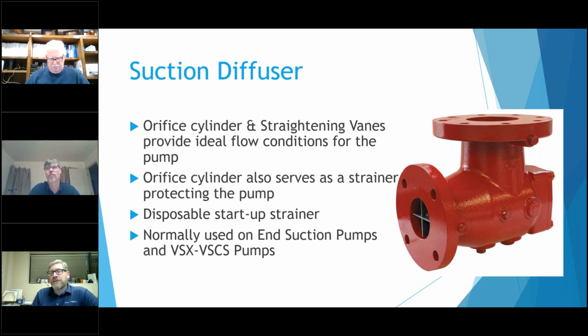Basically this thing's job is just to provide a good flow condition into the end of the pump. If you don't have that good flow condition, you end up stressing out the bearings and the seals, and you end up pushing on one side of the impeller as the water comes in. More water is trying to go into a certain area of the impeller, so it will try to wobble the impeller as the water hits it up here.